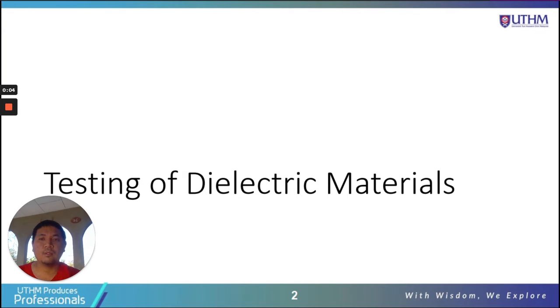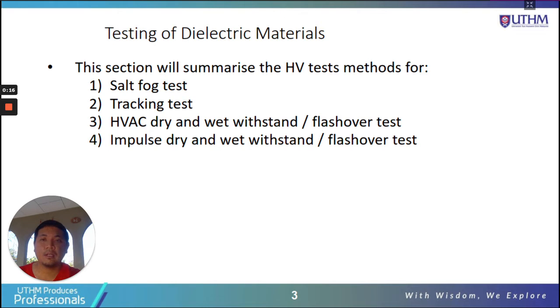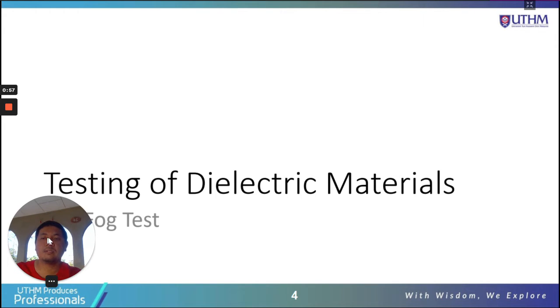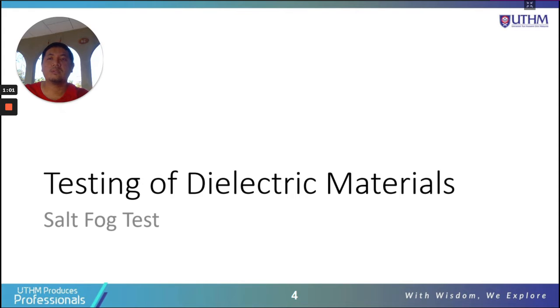Okay, so in this video we will look at other types of electrical tests that we perform on dielectric materials. Besides the tan delta test, insulation resistance test, and partial discharge test, these are some of the tests that we usually perform at the laboratory. We have more than this, but we will cover only four of these: salt fog test, the tracking test, HVAC dry and wet withstand, and dry and wet withstand using impulse as well. All right, so let's look at the first electrical test, which we call the salt fog test.